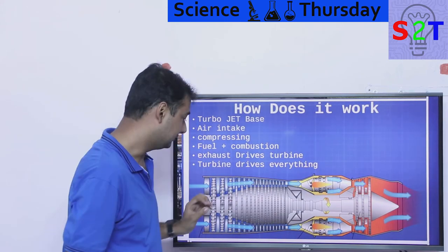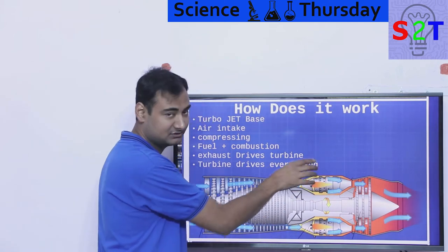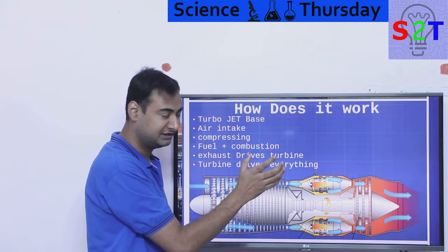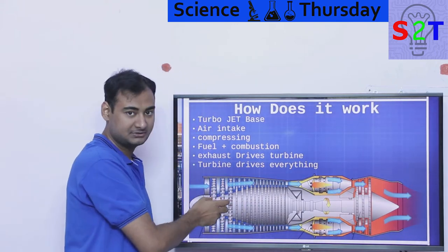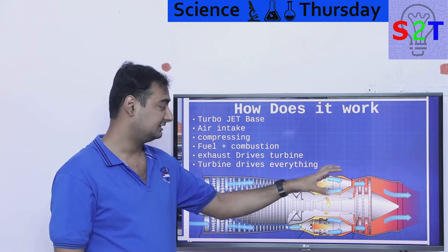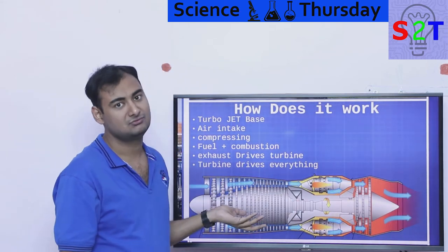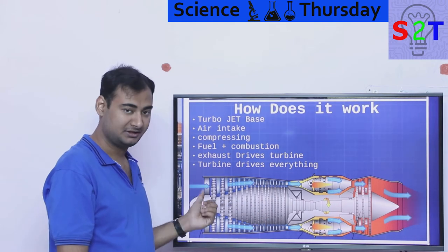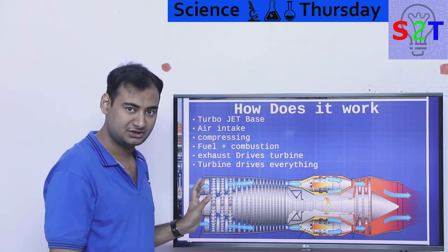It has a lot of physical energy, a lot of thrust. That thrust is converted into rotational energy using the turbine. This is your bread and butter. Till this point, you're not getting anything out of it. The moment the hot fast-moving gas hits the turbine, it rotates the turbine, the turbine spins the compressor. It's a self-fulfilling system. If this turbine is generating 1000 horsepower, the compressor will only consume 200 horsepower. So this turbine, you can connect it to anything. This is now connected to your generator.